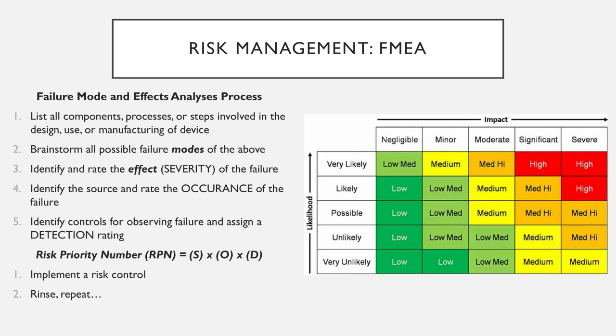There could also be packaging design within a medical device. If you're worried about, hey, what happens if a package gets broken and what was once sterile now becomes not sterile because there's a little rip in the package. Okay, you might brainstorm a way to mitigate that and come up with a special package that has sterility indicators built in. So you just brainstorm any possible thing that could go wrong at any stage of that process, and you start collecting all those particular risks. Step three is to understand the rate and effect, so the severity of that failure. How bad would compromising the sterility of this package be? Is it a life and death situation?